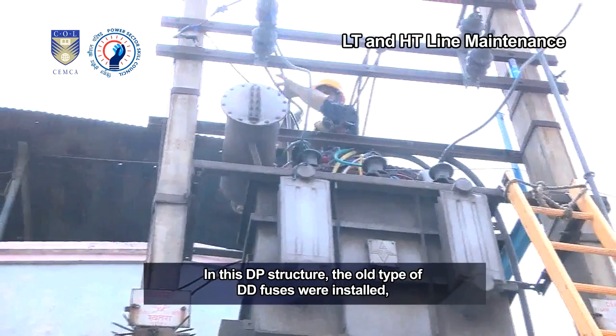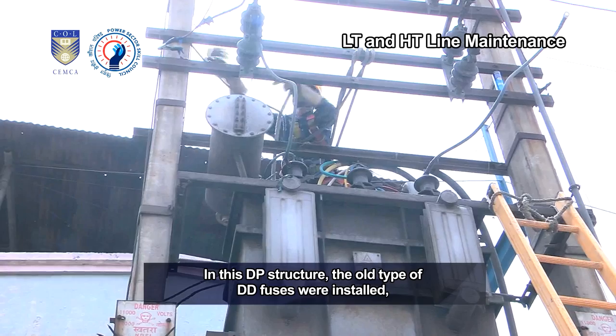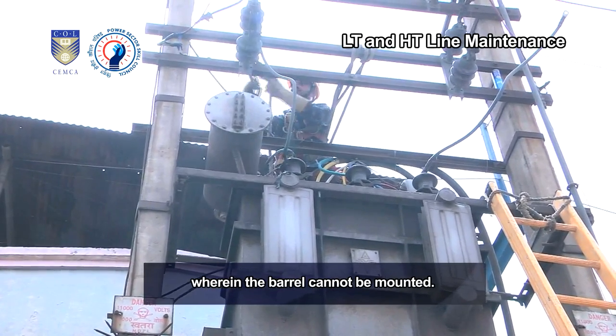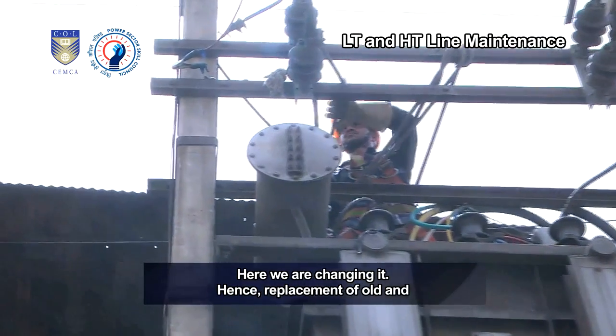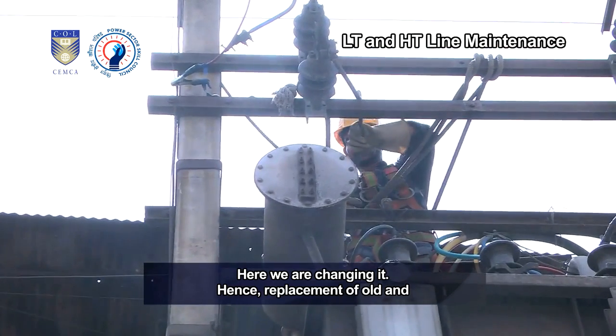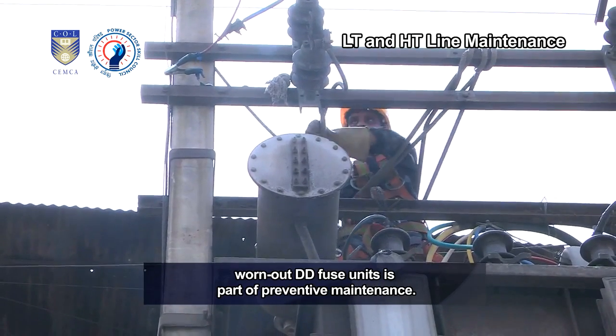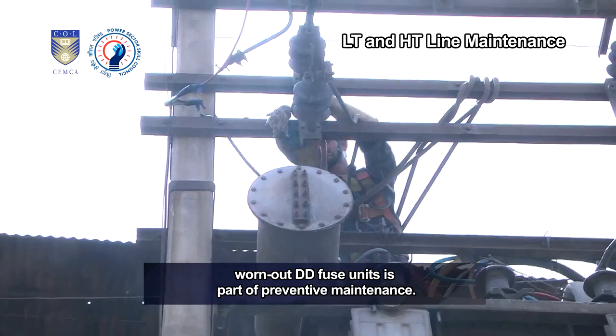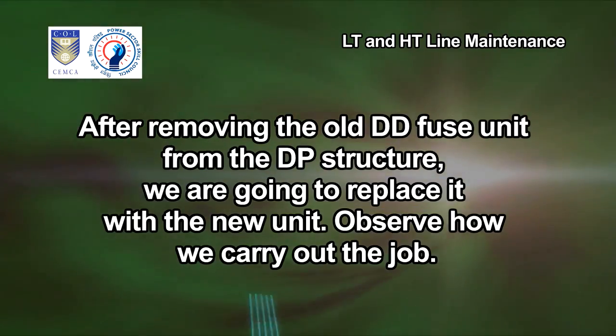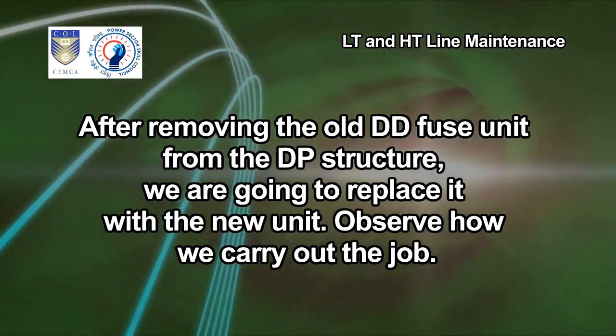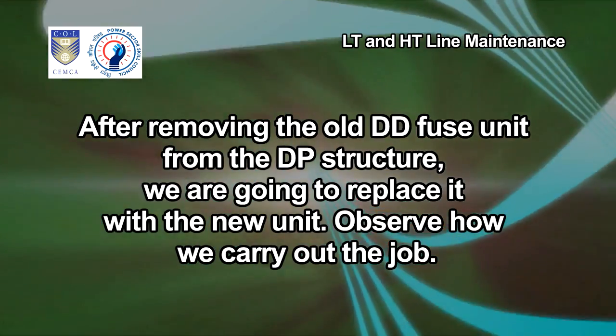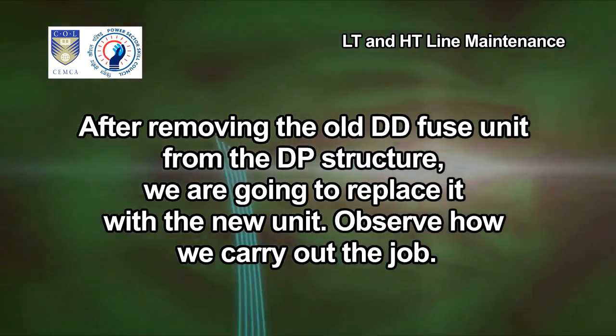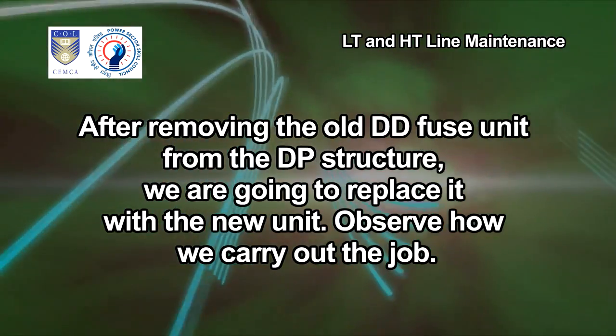In this DP structure, the old type of DD fuses were installed, wherein the barrel cannot be mounted. Here, we are changing it. Hence, replacement of old and worn-out DD fuse units is part of preventive maintenance. After removing the old DD fuse unit from the DP structure, we are going to replace it with the new unit. Observe how we carry out the job.